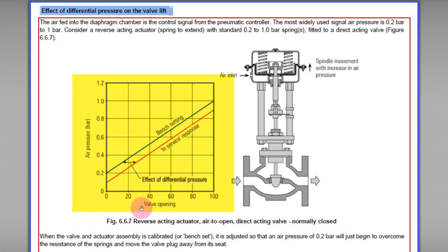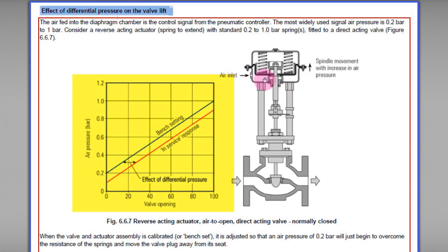For the direct acting actuator, this graph shows the relationship between valve opening and instrument air pressure applied to the actuator. When we supply more than 0.2 bar (or more than 3 psi), the valve will start to open. You can see from the graph that anything above that pressure begins to open the valve.